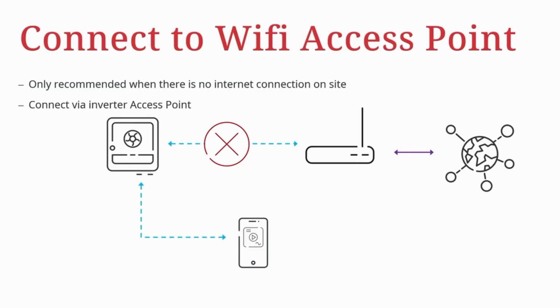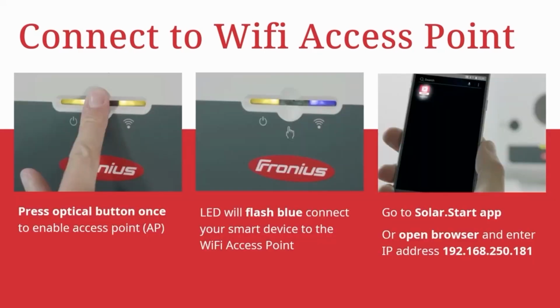So first of all, if we're going to connect directly to the Wi-Fi access point, the main reason you would do this is if you don't have an internet connection on site. The only way to communicate with that inverter is directly with the device. So you need to go to the inverter, enable the Wi-Fi access point, and then you take the Solar Start app, connect to the inverter's Wi-Fi access point, and you can use the Solar Start app to program the device as needed.